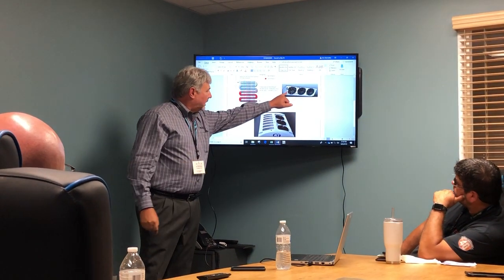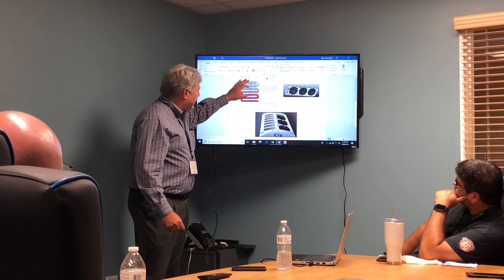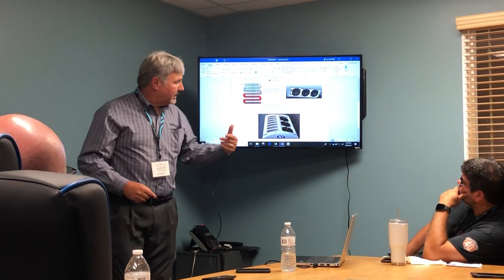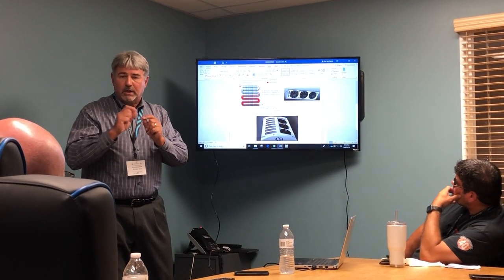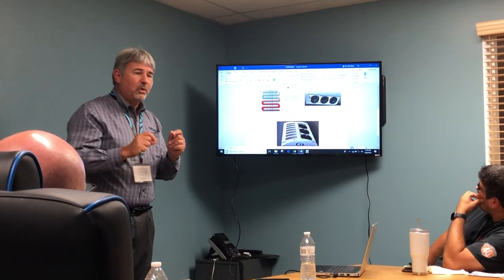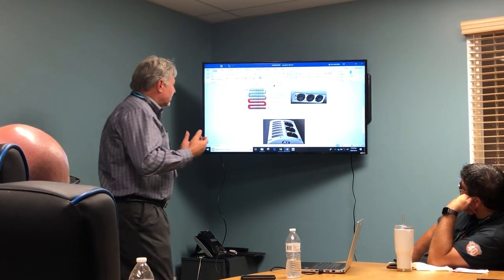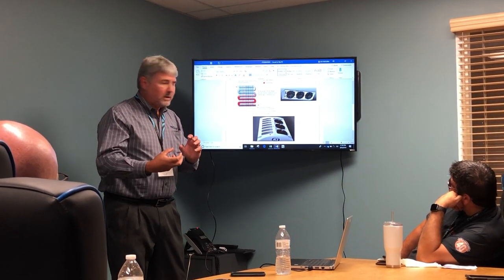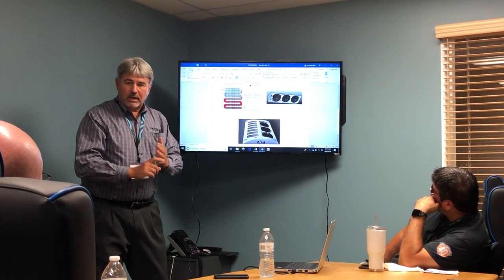If one of these fans starts to go, there's not as much air being pushed, and this vapor isn't condensed into a liquid. And there's a sight glass on there too, on the dryer, on the condenser, and I'll show you what that is here. But it'll start to show bubbles, and those aren't actually air bubbles, those are gas bubbles, because things aren't condensing, the refrigerant is low, or it's got non-condensables in it. So your condenser is your first stage of the AC system starting to change the refrigerant. So it's important that the technicians evacuate it and do a really good job.